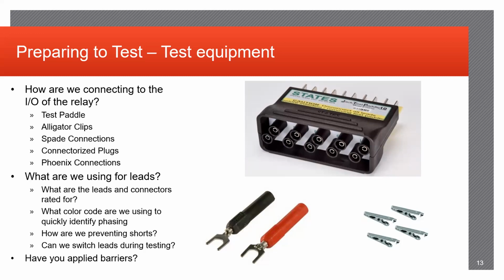Barriers as well. Again, going back to the fact that sometimes stuff happens. You may go out to lunch and not remember specifically where you left off testing, so correctly identifying the piece of equipment that you are going to be testing, and not moving from that point, is extremely important. So stuff like tags, just any type of barricade, whether it's a big old slab of paper across any in-service equipment that you know you shouldn't be touching, or tape surrounding the relay that you will be testing, is extremely helpful. And just another piece of advice for you.